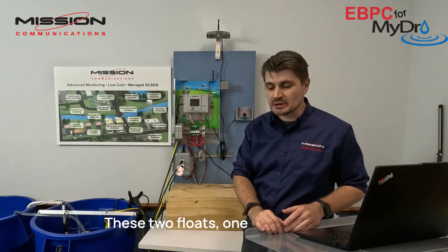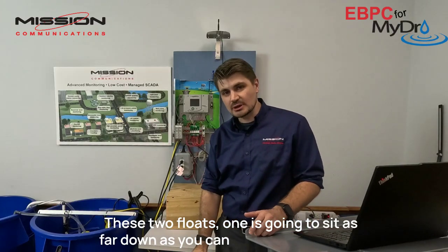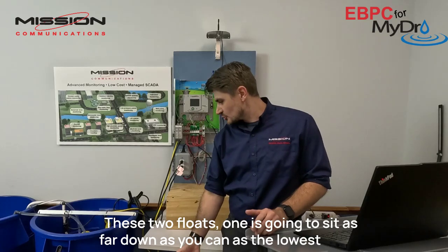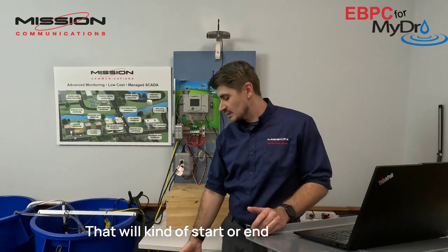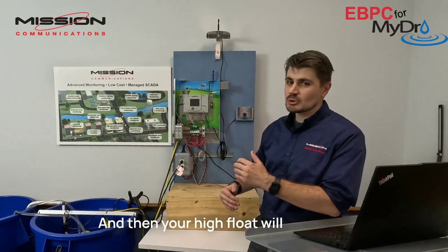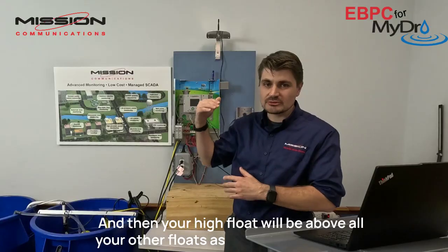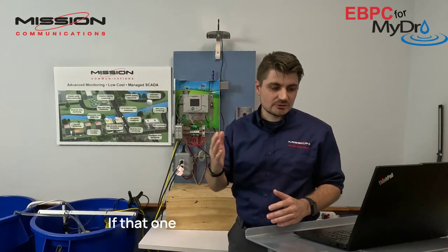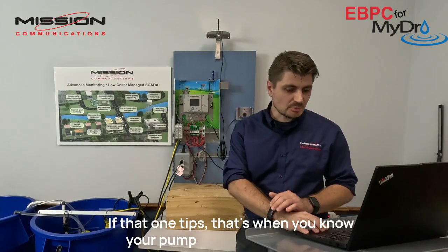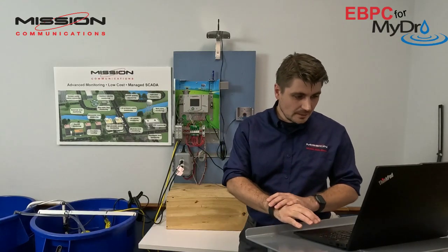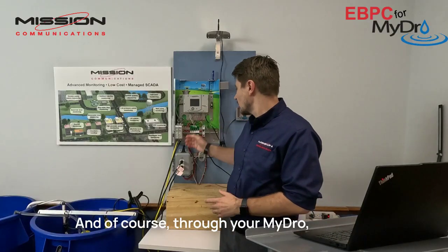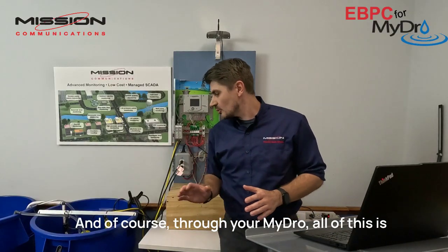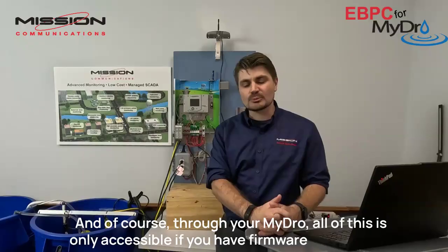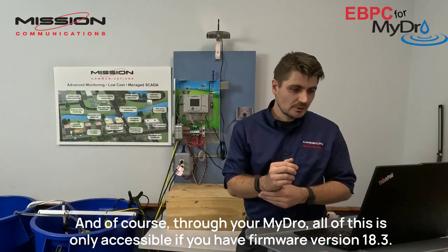These 2 floats, one is going to sit as far down as you can as the lowest point. That will start or end the pump cycle, and then your high float will be above all your other floats as the emergency float. If that one tips, that's when your pump controller has failed. And of course, through your MyDro, all of this is only accessible if you have firmware version 18.3.